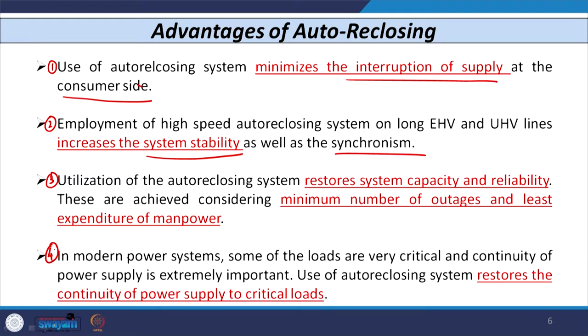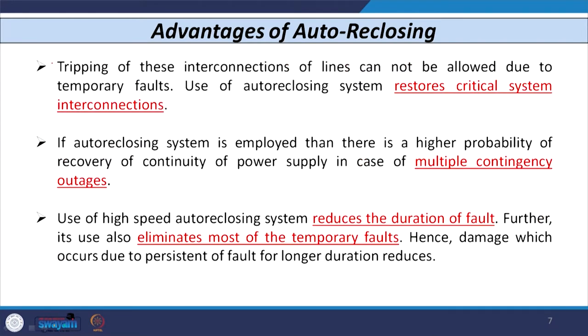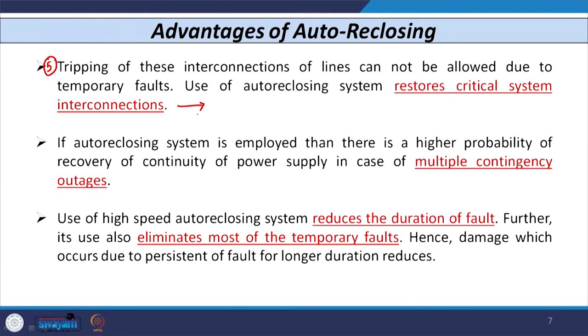The fourth advantage is that some loads in the power system network are very critical — for example, hospitals and military loads — requiring uninterrupted power supply. Auto reclosing restores the continuity of supply for all such critical loads. Another advantage is that tripping of very long or tie lines due to a temporary fault impacts the stability of the whole network, but auto reclosing not only improves stability but also restores critical system interconnections for long EHV and UHV lines.